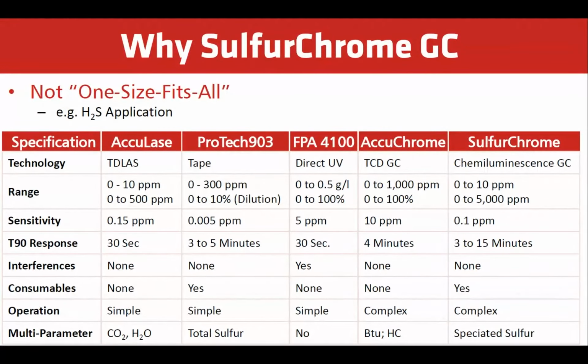ProTech, which is a tape analyzer, the ProTech903. Its range is 0 to 300 ppm without dilution or 0 to 10% with dilution. Sensitivity on the tape analyzer is basically 0.005 ppm, or 5 parts per billion. T90 response is 3 to 5 minutes. Interferences: there is no interference on the tape. Consumable: yes, we have to replace tapes on a monthly basis. Operation is simple. Multiple parameters: it can do H2S or total sulfur, or H2S and total sulfur the same.